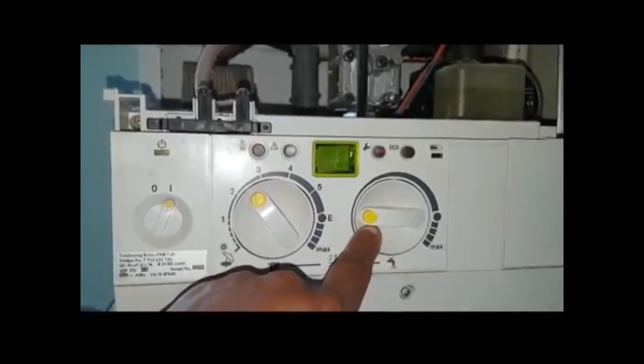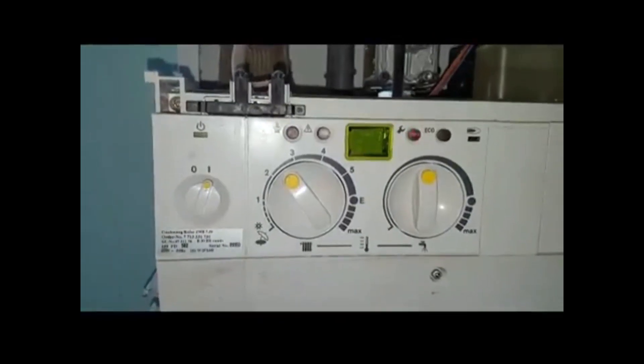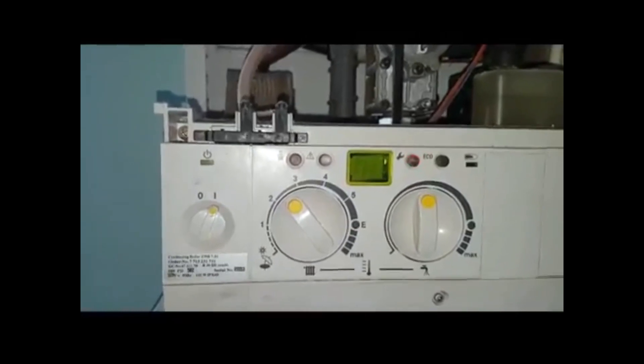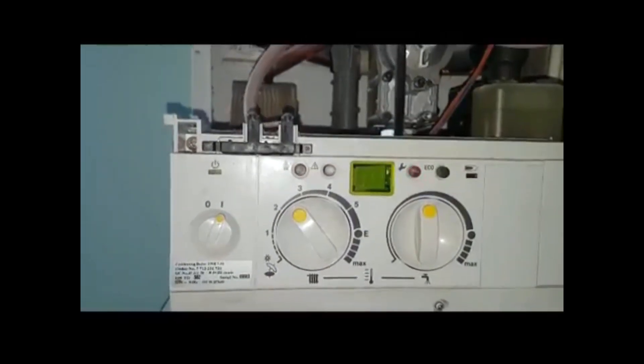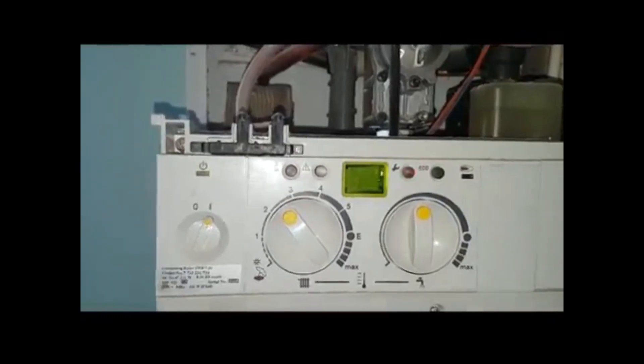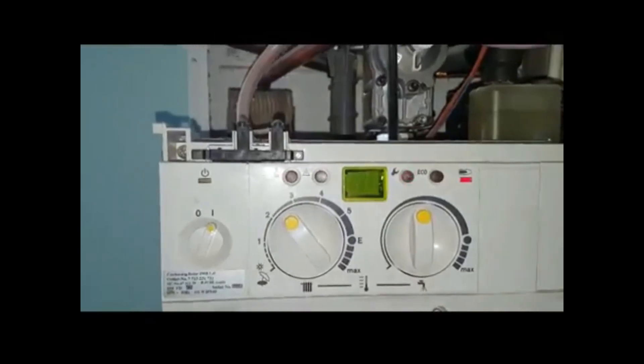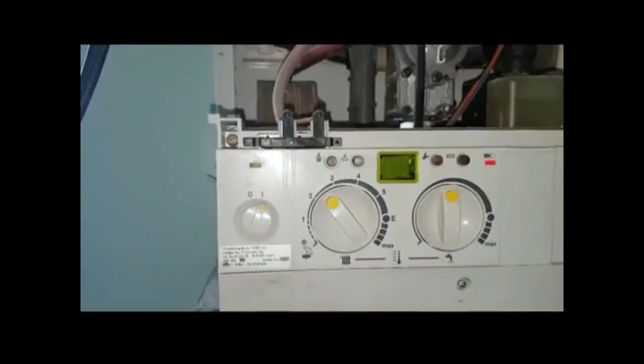Now on position 1, that means it's at the minimum fan speed. So the boiler is now lit up, you can see the burn light come on and the flame. So you now can analyze the gas with the low fan speed.